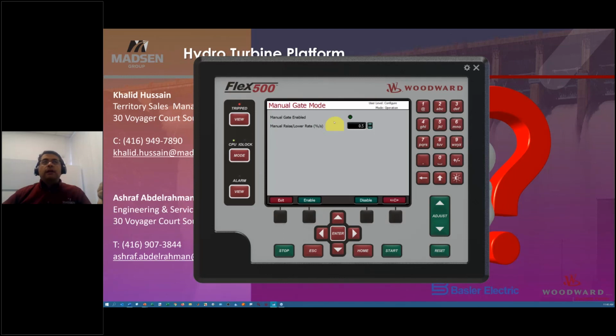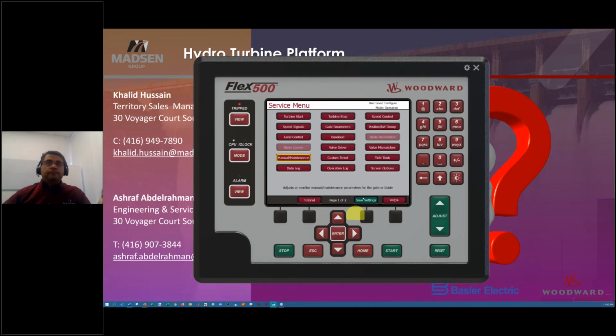Again, we talked about the capabilities, so that if you would like to do some manual opening of the gate itself, if you want to test your gate, you can come here, you hit enable, and then you can test your gate. You can raise and lower, and you can test through the rates. By enabling it, you can do that, but you need to be in the calibration mode, not in the operation mode right now. So once you hit the calibration mode, you will start to see the extra functions coming in.